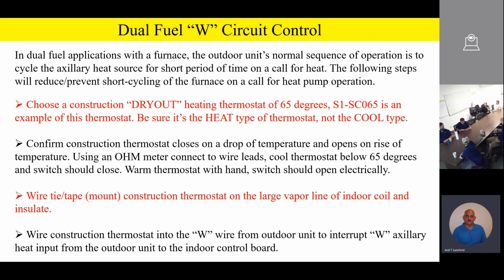Well, team, the next thing we're going to talk a little bit about is dual fuel on a furnace. It's important that we understand that the normal sequence of operation of the outdoor unit is to bring the auxiliary heat on for a short period of time anytime you have a heating call. So what can happen if you have this unit hooked up to a furnace, which is a great product, by the way, for dual fuel, we just need to remember what's going to happen with the auxiliary heat call.